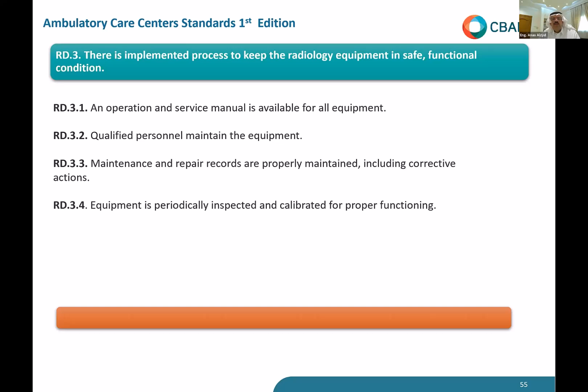Maintenance and repair records are properly maintained, including corrective action. This is with all medical equipment, but it is more emphasized now for the laser and X-ray machines. We need to make sure the maintenance records are there. For example, one major issue we face in healthcare is that sometimes the radiology team gets acquainted with the vendor or the supplier and starts calling them directly without going to the bioengineering or the proper channels. This is very bad, by the way. All the maintenance in your center goes through the bioengineering, or the person in charge of maintenance, so he can keep a proper record of it. Radiology staff should inform him or go through him for all calls or maintenance of the X-ray machines and the laser machines.